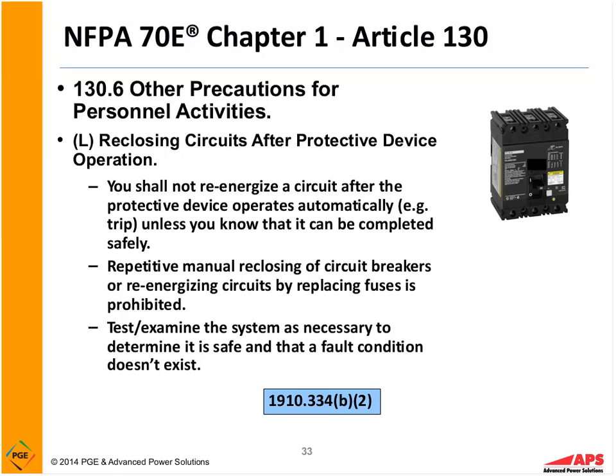Or you can damage the breaker severely. So this is an OSHA and an NFPA 70E requirement: we cannot reset a breaker unless we know it can be done safely. We can't just keep reclosing the breaker into that fault condition. Generally, circuit breakers are only rated to clear a fault at their full fault current rated value 2 times before they need to be replaced.